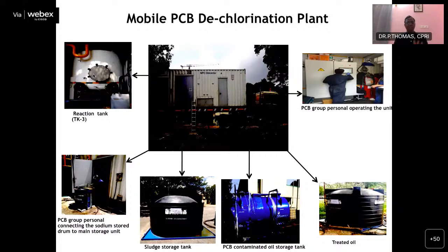When you add sodium dispersion, the sodium reacts with the PCB oil, removes the chlorine, and forms sodium chloride, leaving transformer oil behind. Since we are only dealing with contaminated oil, whatever contamination is there converts into sodium chloride and biphenyl, and the rest remains transformer oil. We always take excess sodium dispersion during the reaction so that the reaction goes to completion.